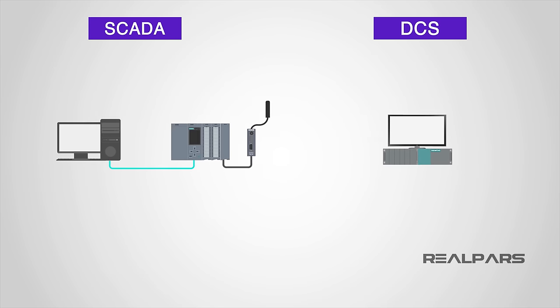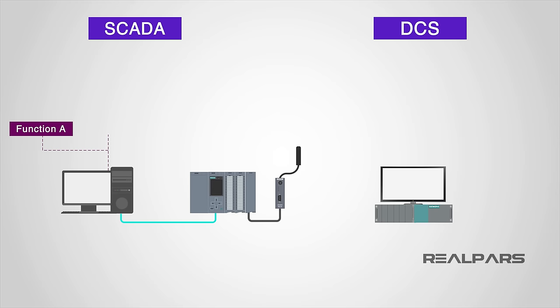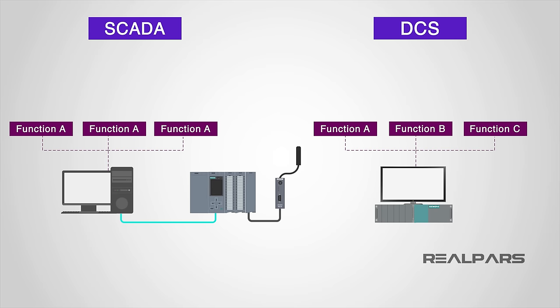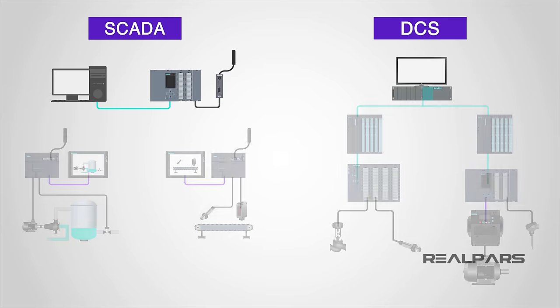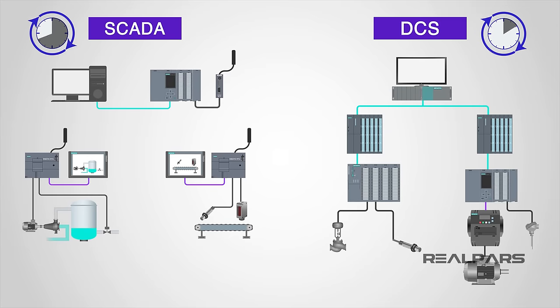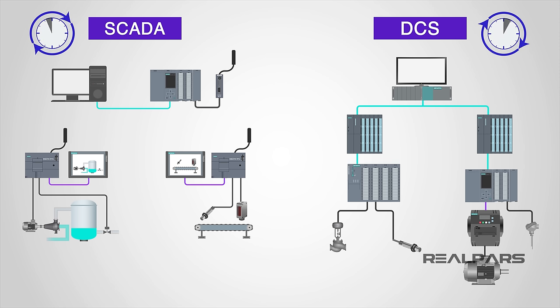While this was more cumbersome in the SCADA implementation, at least in the earlier days, the DCS had many predefined functions that could be customized and deployed for various applications. This didn't eliminate the need to write code; however, it did help facilitate faster integration because less time would be spent writing code for commonly used functions. Processing times are somewhat slower in the DCS versus the PLC/RTU SCADA environment, which could have an impact on processes that are very time sensitive.